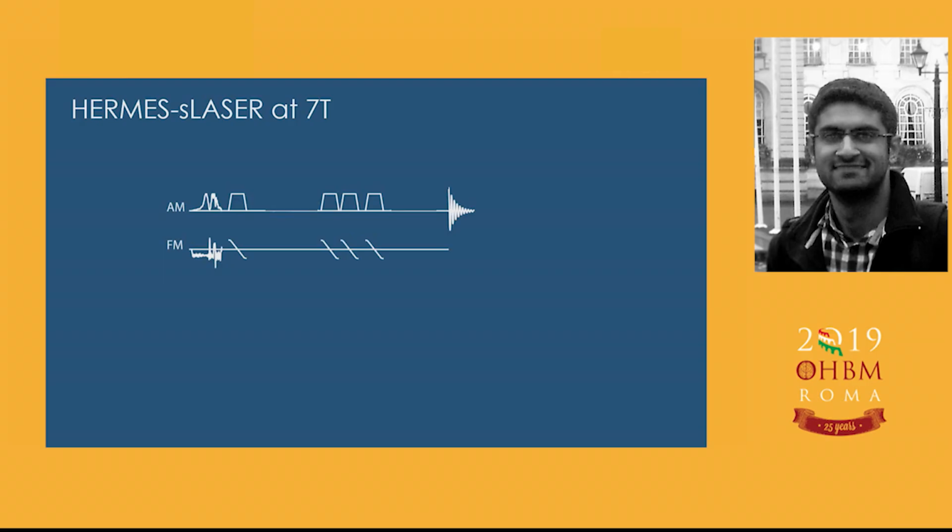So several studies conduct single voxel spectroscopy using the semi-LASER sequence. And how do you get that sequence? You start with a slice selective excitation pulse with frequency modulation, and use adiabatic pulses, which are also slice selective, with frequency modulation. This is where the benefit comes in. This sequence implements adiabatic pulses. They are known to have higher bandwidth, so they reduce your chemical shift displacement error and increase your editing efficiency, but they're also less sensitive to B1 inhomogeneity. So you need to reach a certain threshold, and after that, if it varies, it doesn't matter, because it just requires that minimum amount of B1 to work optimally.